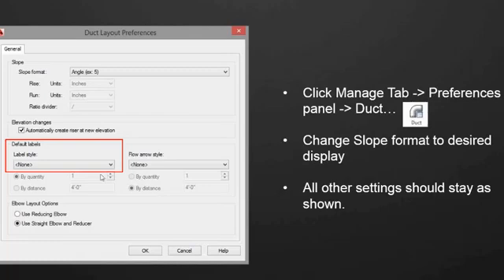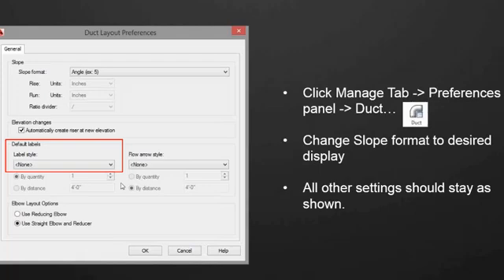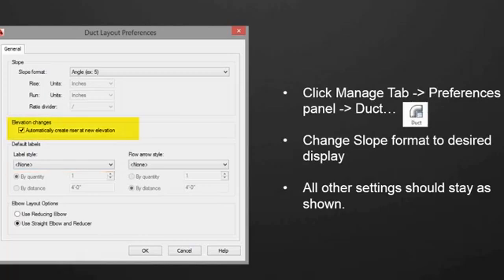Now what you see here is the way that I like to set it up. Because we have auto-tagging for duct, we do not use labels. It will interfere with the tags a little bit. If you have auto-tagging turned off, you could certainly use labels. Labels are entirely different than tags. Usually the labels are constrained to sit right on the duct. You can change that, but you have to change it for each individual label, whereas tags are very easy to move around. So generally, if I'm using auto-tag, I have the labels turned off.